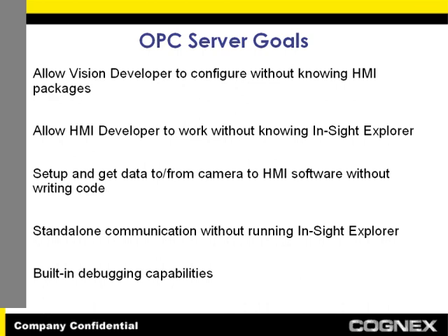Won't there be a need for a memory location for that data in the HMI? No, and that's what's so nice about it. It's just simply referenced by a name. So the tag really only resides in the InSight OPC server. Right. The OPC server knows where that data is. Okay. But the programmer doesn't have to worry about that. It's all underneath the hood. All right.